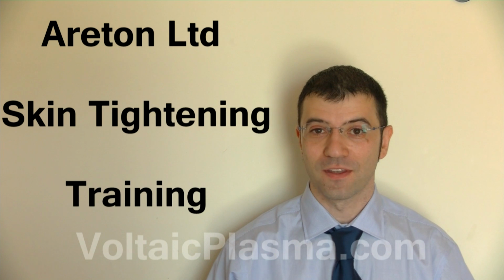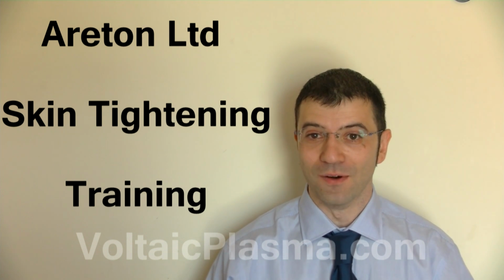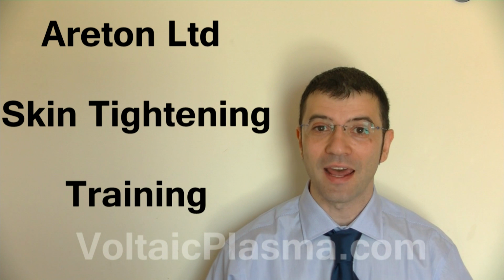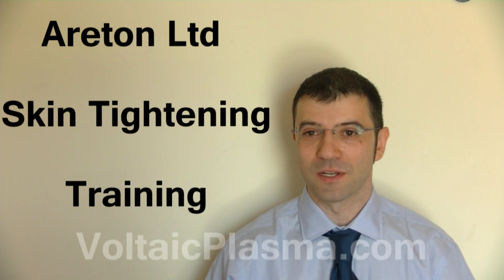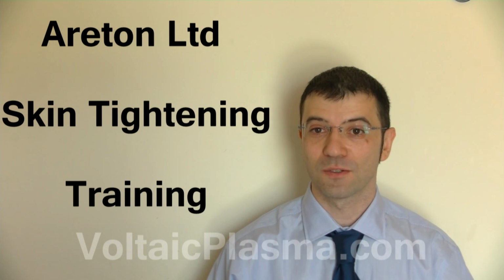As you have seen in our previous video, the carbonization effects of electric arcing are dependent on the way you apply the arc, regardless of the power setting of the equipment. The minimum power level is designed to allow the user to perform the cosmetic treatment while also ensuring the carbonization effects are minimal, and hence even a slightly erroneously prolonged exposure to the arc would not cause significant unwanted damage to the dermis. Please be aware that despite any low power setting, excessively prolonged exposure to voltaic arc will eventually lead to irreversible damage to the dermis or even injuries.